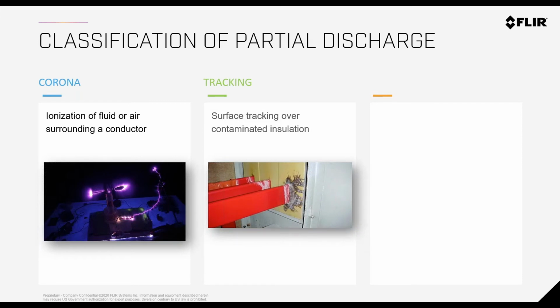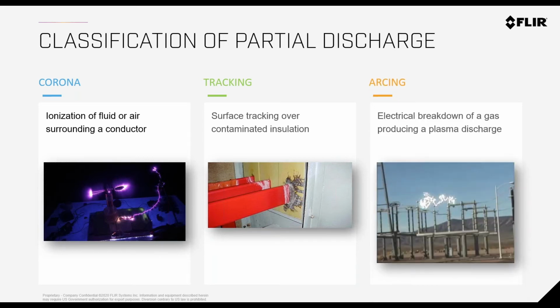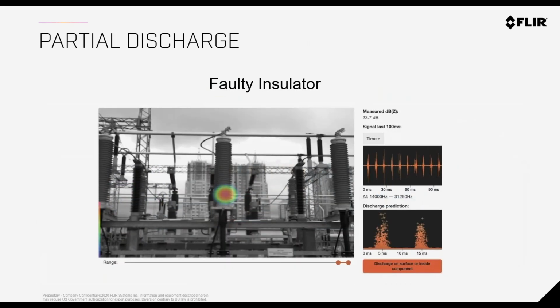It can also detect tracking, surface tracking over contaminated insulation - there's an image of that right there. These things, if they go undiagnosed, usually result in big catastrophes. Then there's arcing, when you have electrical breakdown of a gas producing a plasma discharge. If you have leaks between connections or connectors, like an SF6 leak, some of these can cause an arc flash, which is going to be a bad day for a lot of different people. Here are a couple examples of that.